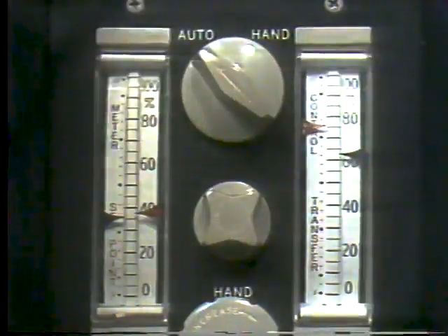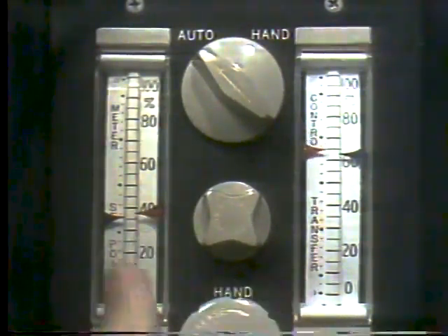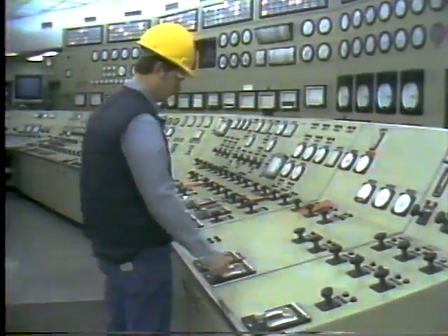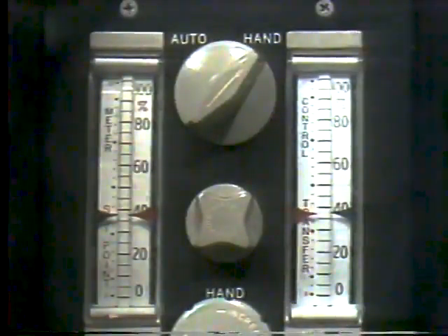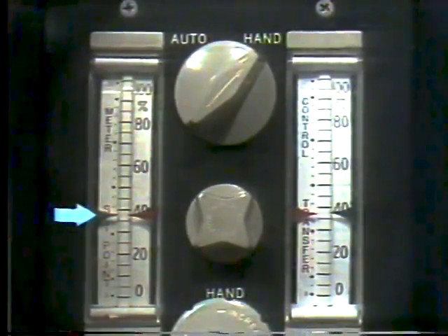Now, once the technician knew this, he realized that the engineer's settings were a little off, so he decided to tune the system from scratch. After deciding what to do, the technician adjusted the hand station for a bumpless transfer, switched the control system back to manual, and adjusted the cooling water temperature back to the correct control point of 37.5%.